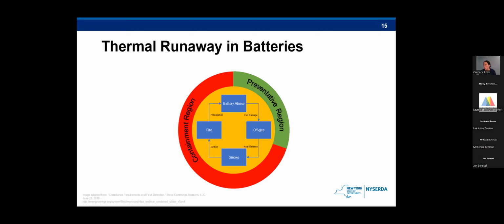There is also what we're referring to as the preventive region and the containment region, based on how the risk has escalated. For example, if there is some sort of battery abuse, a puncture or overheating of some sort, that could cause cell damage, and the system may begin to off-gas. This is still in the preventative region on the chart. And on the next slide, we'll go through the different protections in each region.